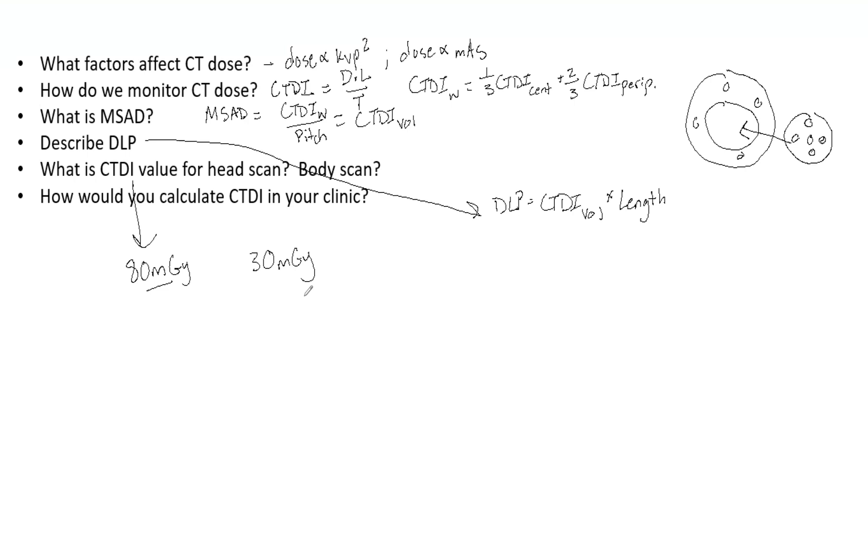And then how would you calculate CTDI in your clinic? As I kind of mentioned over here, you're going to use a pencil chamber in a lucite phantom. That's typically what these are. And these have different circular phantoms.